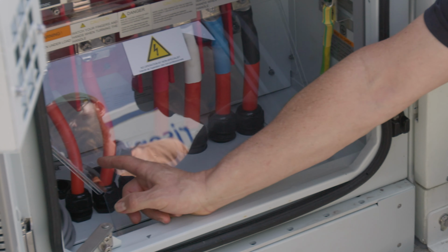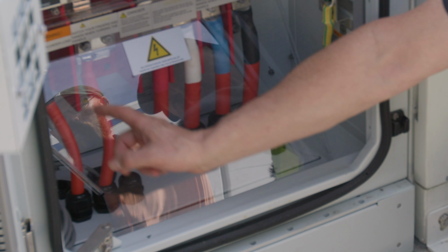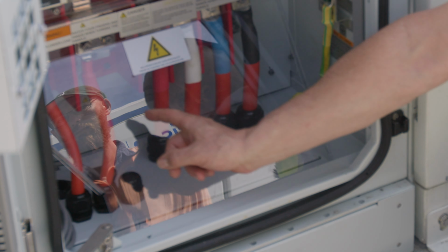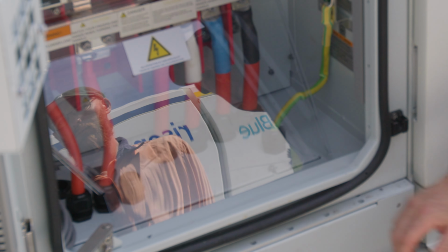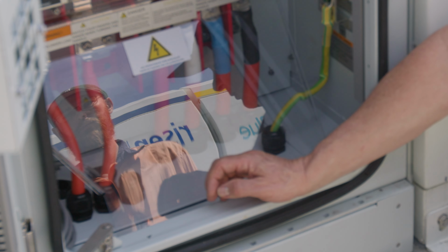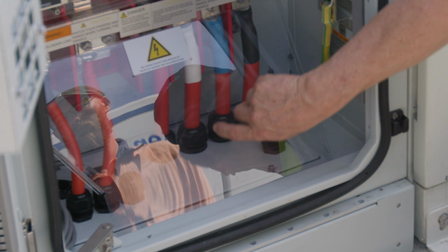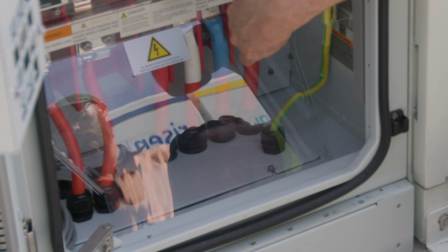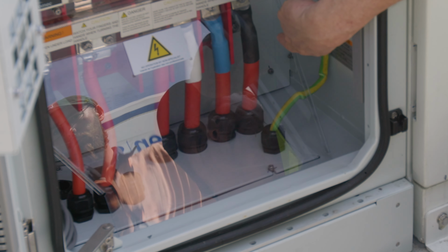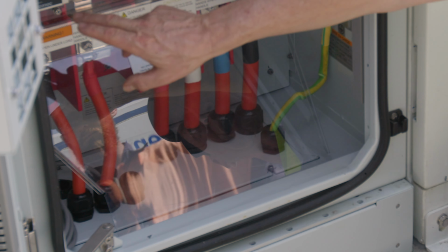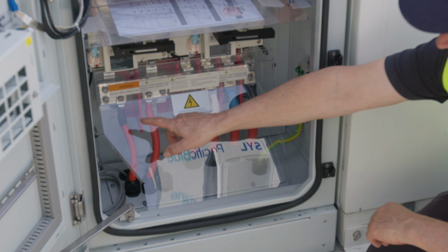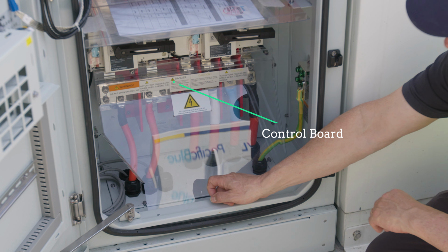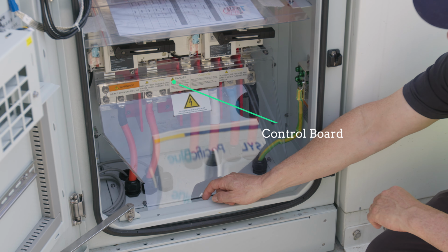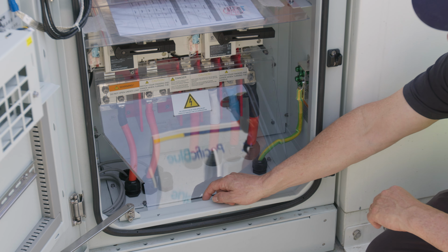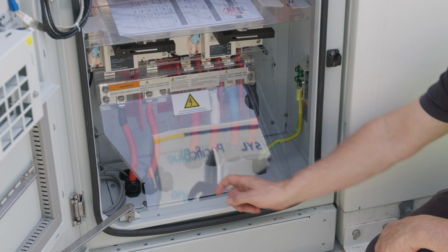Now, if we come down here, you've got your neg here and your pos here, and you can see by the colour of the heat shrink. There's a perspex cover here, obviously, from a protection touch voltage perspective. Now we've got the phases, the red, white and blue, and then the neutral here. Can you just explain what's going on in this section over here? That board there is basically the control board for the inverter. It interlinks to each inverter so they can all talk and operate as one system. All 5 of these inverters are connected together, daisy chained, and they go back to a site manager which will operate all 5 inverters as one unit.